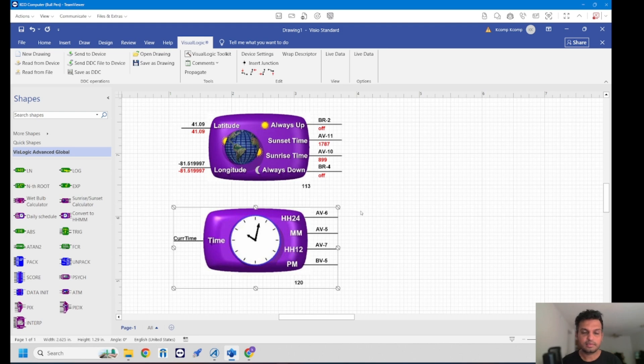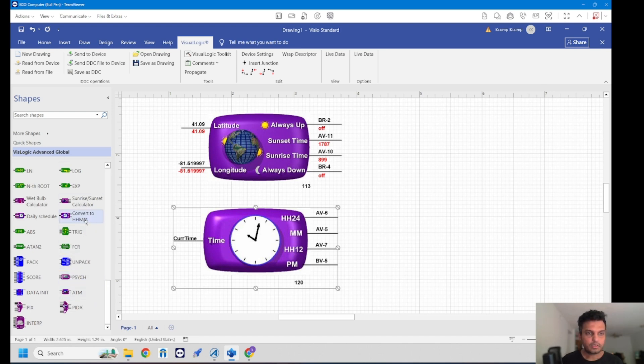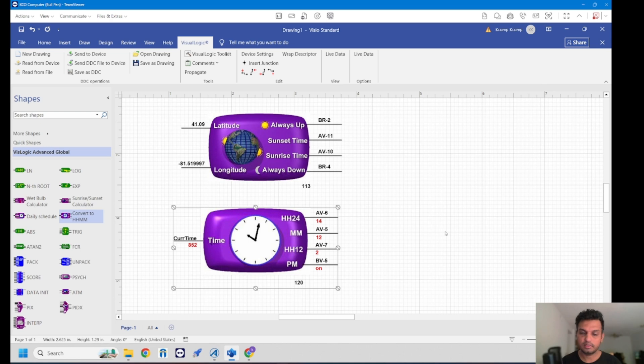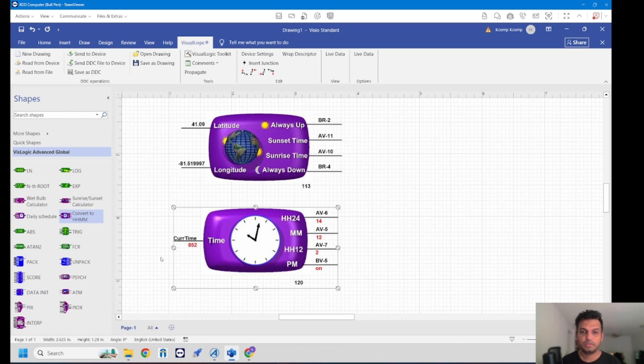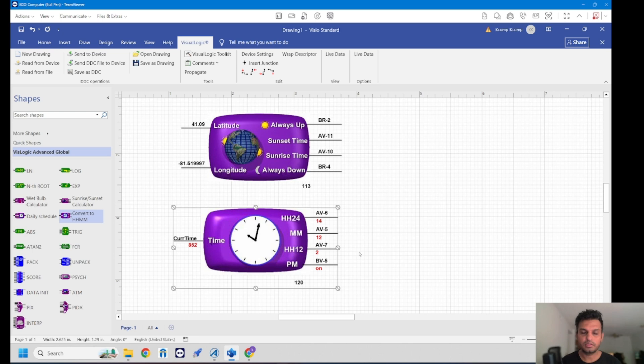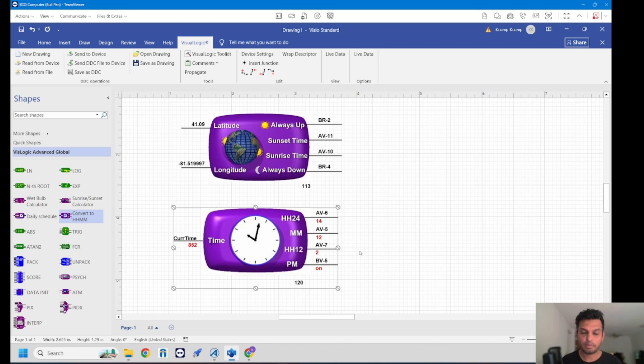The last and the third function block is the conversion function block which you can see here. The conversion function block, whatever your current time, which is currently when I'm recording this is about 2:12, which gives me an expression value of 852 and converts that to 24 military or 12 hour format. So 24, you could have a different AVs under each output and use them for your calculations or your comparison.